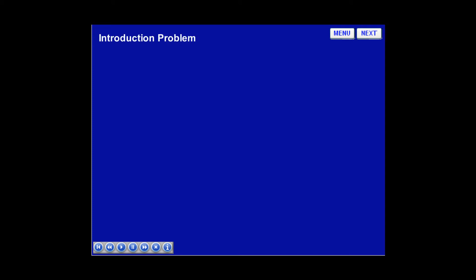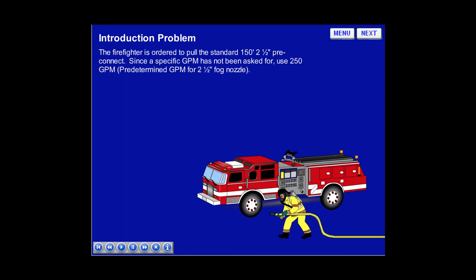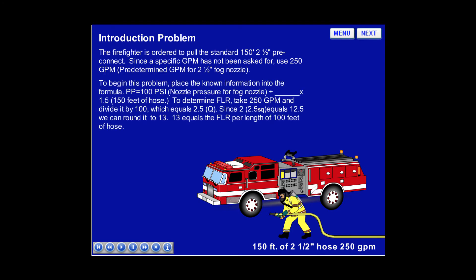The firefighter is ordered to pull the standard 150-foot, 2.5-inch pre-connect. Since a specific GPM has not been asked for, use 250 GPM, which is the predetermined GPM for a 2.5-inch fog nozzle. To begin this problem, place the known information into the formula.